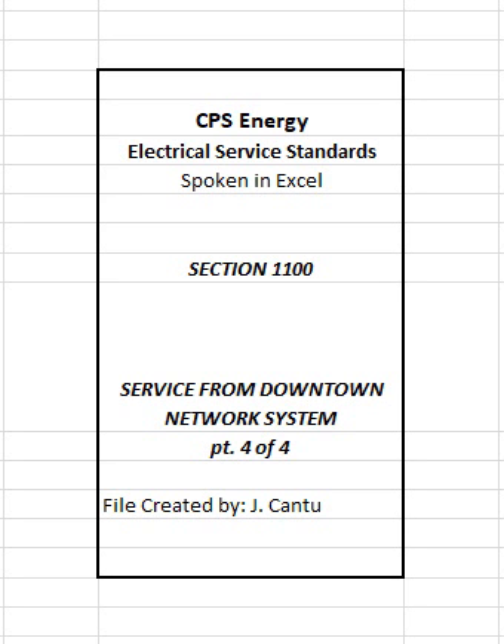Note: designs incorporating load-side disconnect after CPS Energy metering equipment, to accommodate loads that will be switched off frequently or switched off for an extended period of time, will help limit damage to sensitive metering equipment and unnecessary downtime for customers. See the following figures or tables in the specification manual. Figure 1101 typical downtown network system service with CPS Energy grid-tied disconnect above ground. Figure 1102 typical fuse pad detail for CPS Energy secondary grid service from the downtown network system. Figure 1103 typical fuse pad detail for CPS Energy transformer vault/room service from the downtown network system.